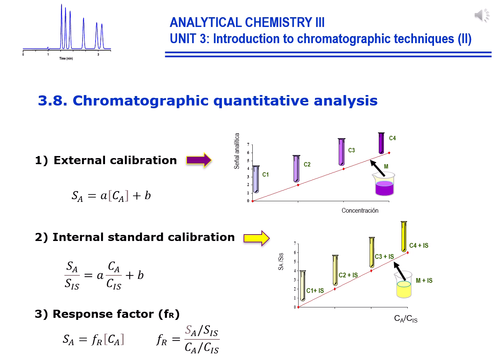Internal standard calibration, where a fixed concentration of a compound similar to the analyte, called the internal standard, is added to all calibration standards, and the ratio of the peak area of the standards versus the ratio of standards concentration are plotted, performing a linear regression as well. The sample is prepared in the same way as the standards and quantified by the peak area analysis.